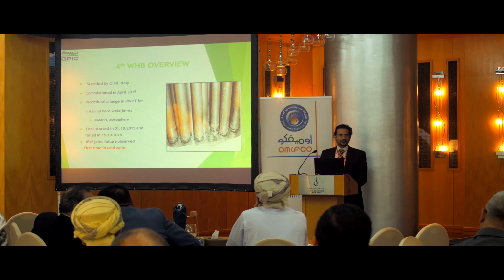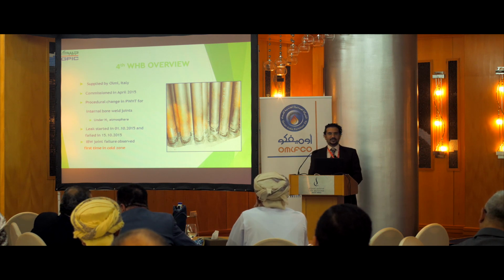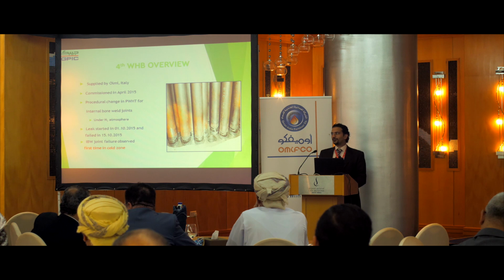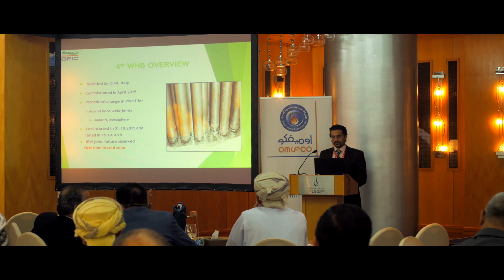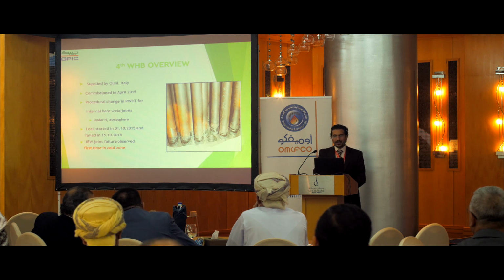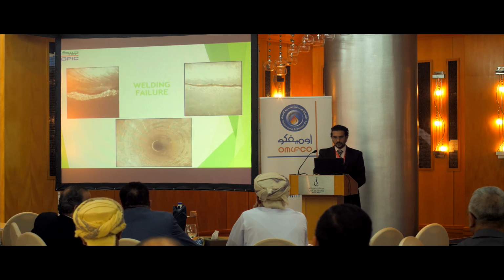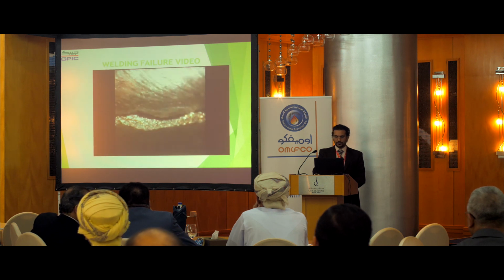However, 6 months after startup, a leak started. We found it from the conductivity that was increasing. And 2 weeks later, the tube failed. This is the first time we got a leak in the cold zone. So this is a welding failure, after we looked through the tubes with borescopy.